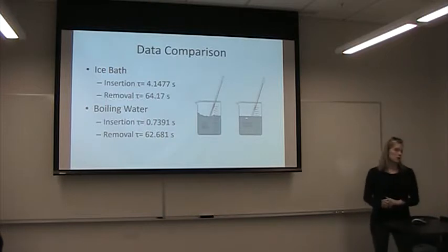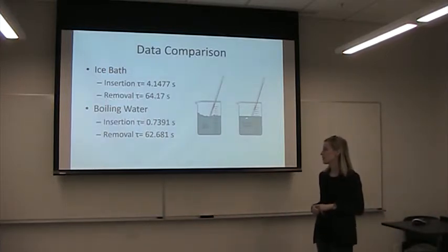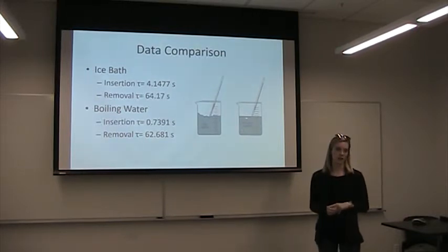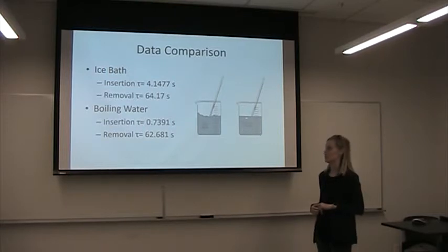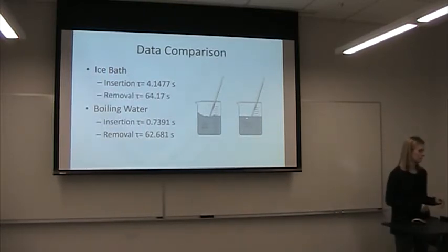The data that we compared it to was the boiling water, and the boiling water insertion time constant was 0.7 seconds, which is a lot quicker than the ice bath. And the removal time constant was 62 seconds, which is comparable to what we got for the ice bath.